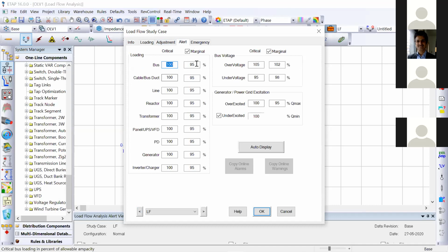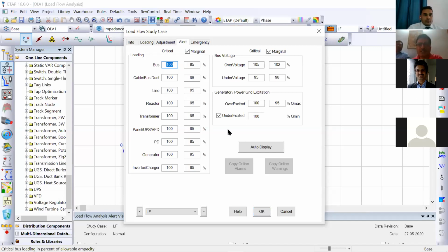And this is the alert. As we explained earlier, the bus turned orange, right? So that was because of this setting. So you can have customized settings for knowing the under voltage. Say you are modeling the distribution system of a city, and there are 1,000 buses in the system. Because of particular loading conditions, which buses will go under voltage, and for that, what will be the optimal capacitor placement or SVC, where to locate, and you can realign the system by changing the parameters. So that can be one of the uses of ETAP you can do efficiently. So all these input and output parameters are in your hand, so that you can model and get the result fast. That is basically the strength of this software.